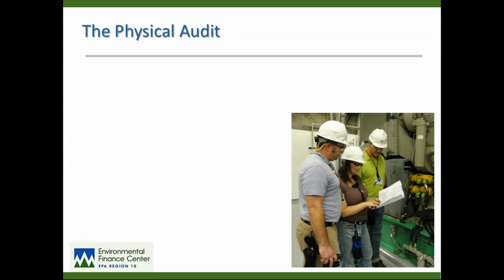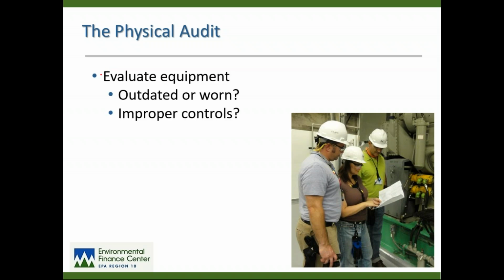So the physical audit starts with actually getting your hands on the equipment. Look at all of your equipment. You want to create an inventory of all your different equipment, which would be pumps, motors, lighting, air conditioners, heating units, and actually what we call plug loads, which are all of the 120 volt items that we have plugged in at the office: battery chargers, computers, lamps, lighting, projectors, things that are not normally connected with actual production or treatment of water, but are necessary to the operation of the business. Printers, things like that. We call those plug loads.